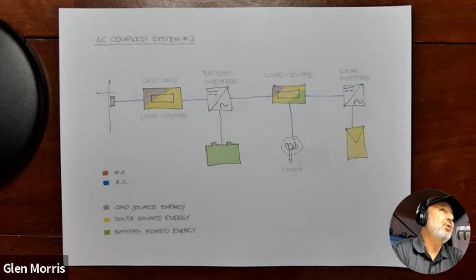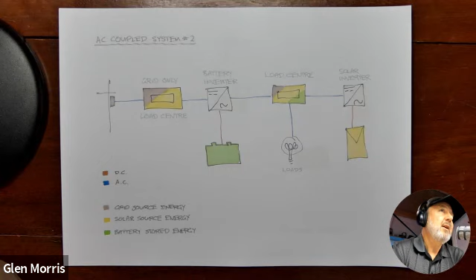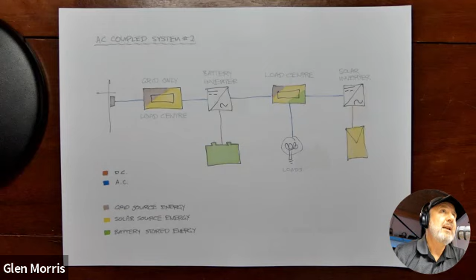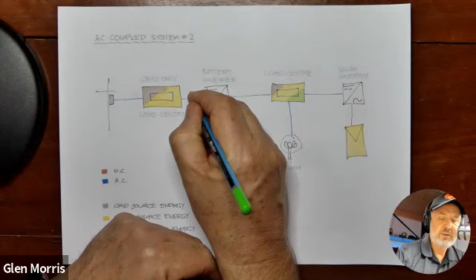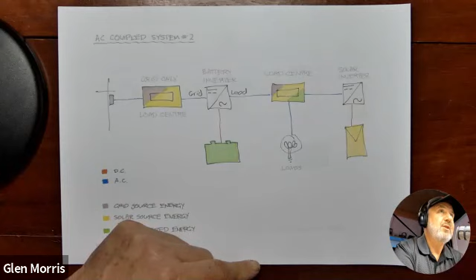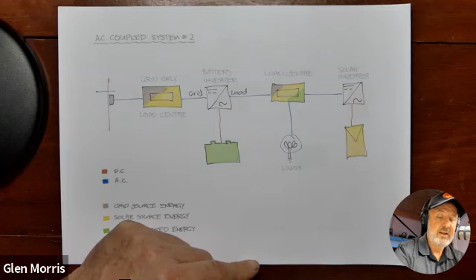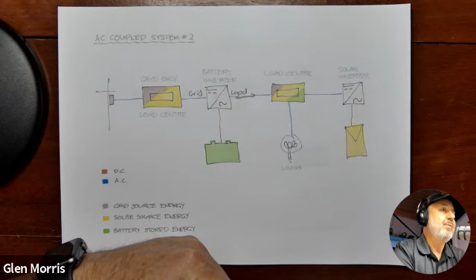Now I call this AC coupled number 2. This is not a very common configuration, I should say, but it's where you have 2 inverters like in the previous picture, but now the battery inverter has 2 AC ports. It's got a grid side, and it's got a load side. So it's not just a single port AC battery inverter. It's got two dedicated ports, and it's got the ability to receive energy or export energy on its load side. So it's not just an inverter that outputs power, it can receive power from another source, in this case the solar inverter.